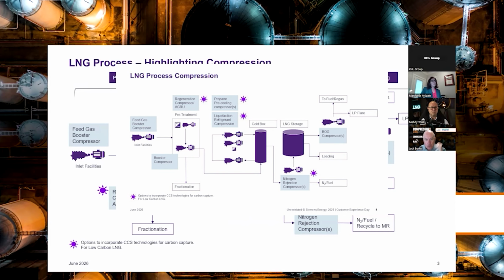So just quickly highlighting, in a very simplified way, the LNG process, maybe for those who are less familiar. I'm not a process engineer. Mehdi's probably way more schooled in this than myself, but just to highlight where we see compressors in an LNG plant. We always talk about the heart of the plant right here in the middle, and that's the liquefaction space. And that's where you have your process, and this one highlights more of a C3MR type style, where you have a propane pre-cooler and refrigerant compressors, mixed refrigerant, and a coil wound heat exchanger.